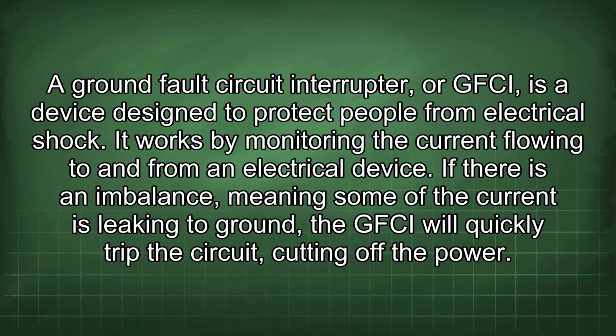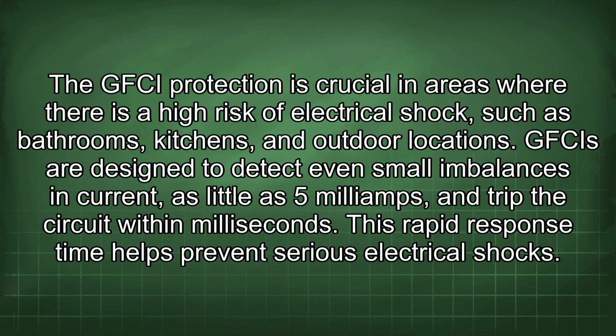It works by monitoring the current flowing to and from an electrical device. If there is an imbalance, meaning some of the current is leaking to ground, the GFCI will quickly trip the circuit, cutting off the power. The GFCI protection is crucial in areas where there is a high risk of electrical shock, such as bathrooms, kitchens, and outdoor locations. GFCIs are designed to detect even small imbalances in current, as little as 5 mA, and trip the circuit within milliseconds. This rapid response time helps prevent serious electrical shocks.